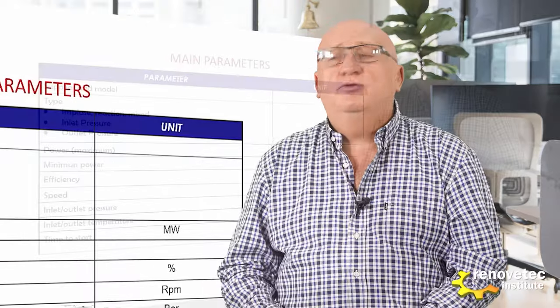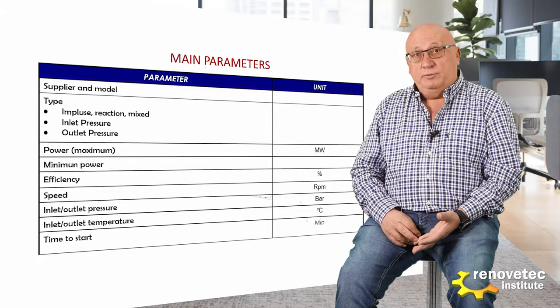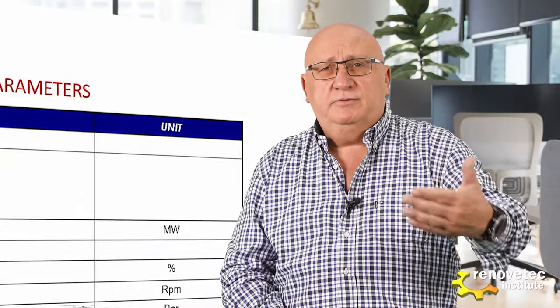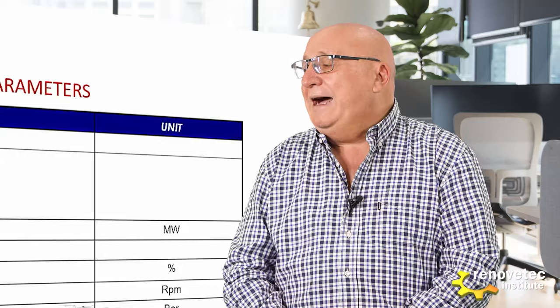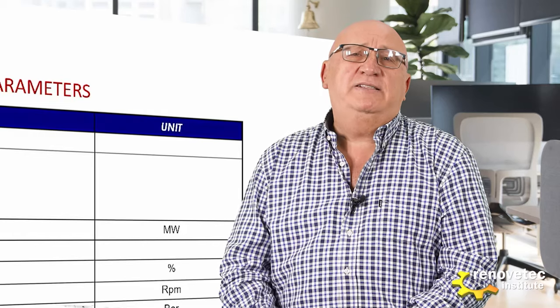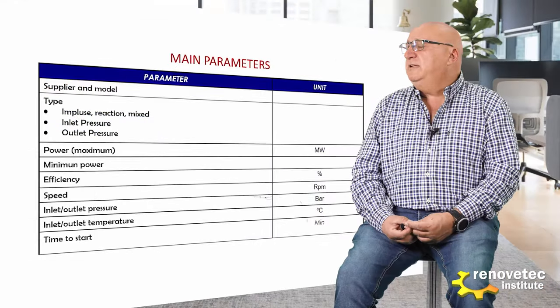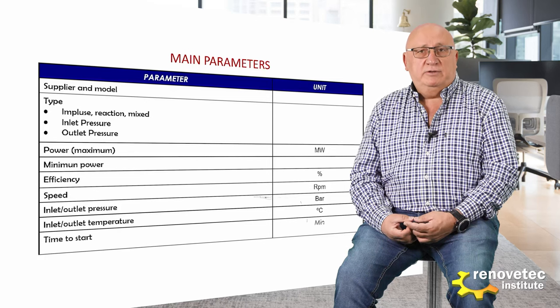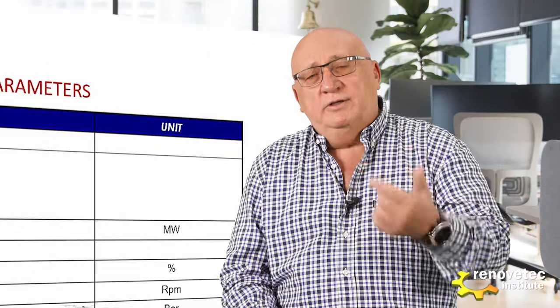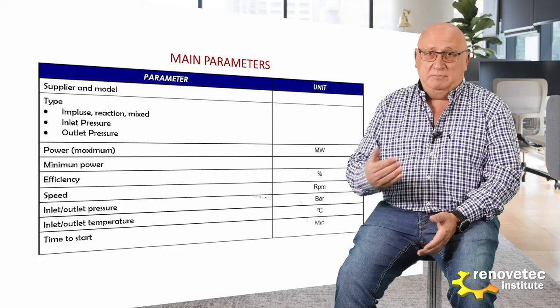The main parameters of a steam turbine include: the supplier model, the type of turbine — impulse, reaction, or mixed — the inlet pressure classification (high, medium, or low pressure), and the outlet pressure (condensing or back pressure). One very important characteristic is the power, and also the minimum power or technical minimum power, which is the minimum power needed to maintain the turbine rotating. Normally in a steam turbine this is around 10% of the maximum power.